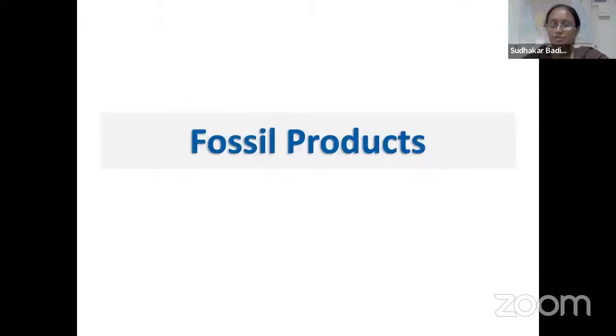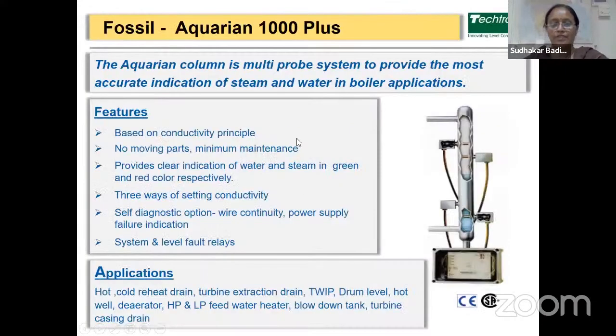These are the Fossil products which are used for boiler applications from our channel partners, that is Fossil from Canada. This is an Aquarian 1000 Plus. This is an Aquarian column which is used with a multi-probe system to provide the most accurate indication of steam and water in boiler applications. This is based on a conductivity principle, and a number of probes are there. And for this Aquarian 1000 Plus, maximum probes will be 4 numbers.